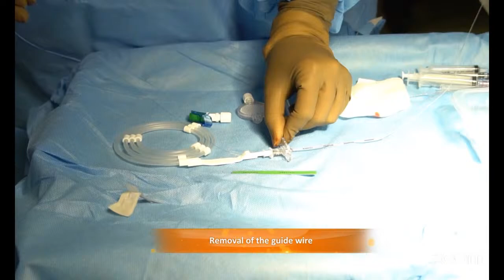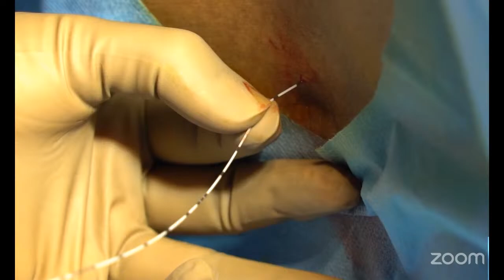We tend to place the entire frame onto a tray beside the patient and remove the guide wire, leaving only the catheter inside the patient. The connector is fixed to the end and the catheter is adjusted so that only about 3 or 4 centimeters lies within the intrathecal space.